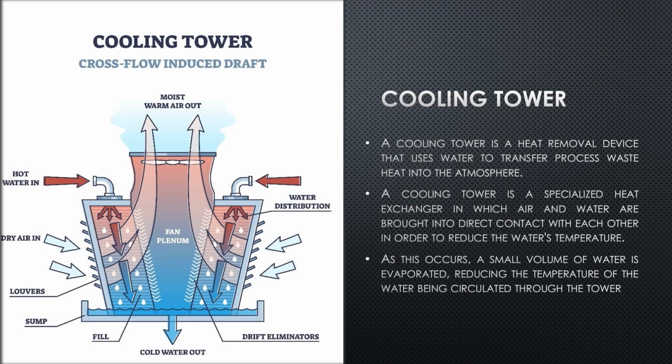Before going on to more detail of this credit, we need to know more about cooling tower. Well, a cooling tower is a part of HVAC system and is a heat removal device that uses water to transfer process waste heat into the atmosphere. A cooling tower is a specialized heat exchanger in which air and water are brought into direct contact with each other in order to reduce the water's temperature. As this occurs, a small volume of water is evaporated, which reduces the temperature of the water being circulated through the tower.